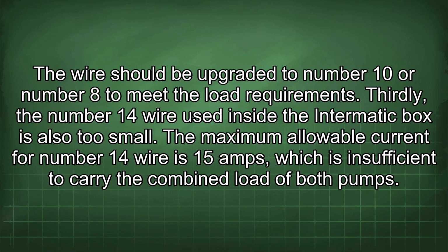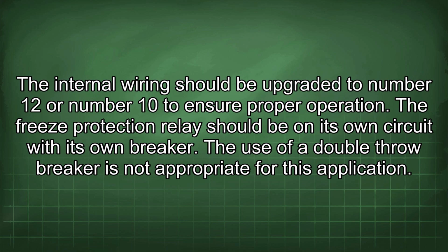Thirdly, the number 14 wire used inside the Intermatic box is also too small. The maximum allowable current for number 14 wire is 15 amps, which is insufficient to carry the combined load of both pumps. The internal wiring should be upgraded to number 12 or number 10 to ensure proper operation.